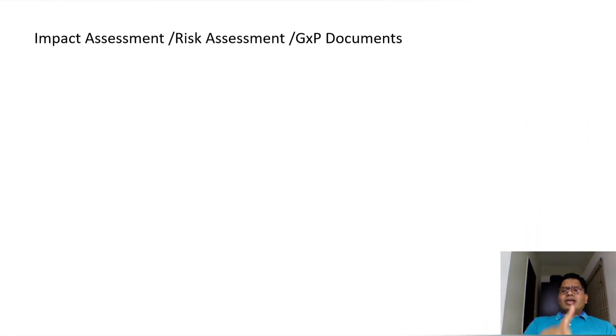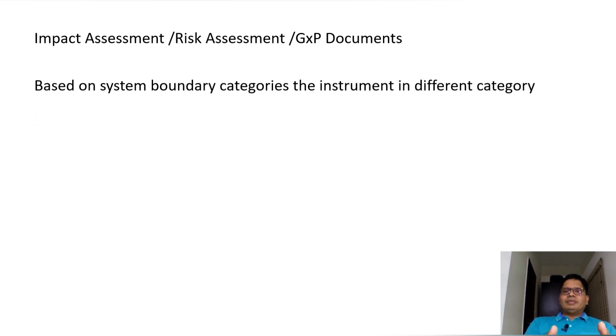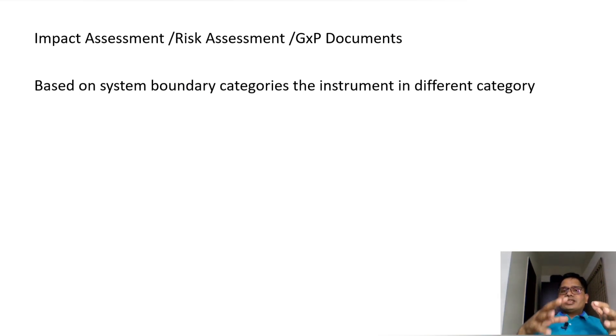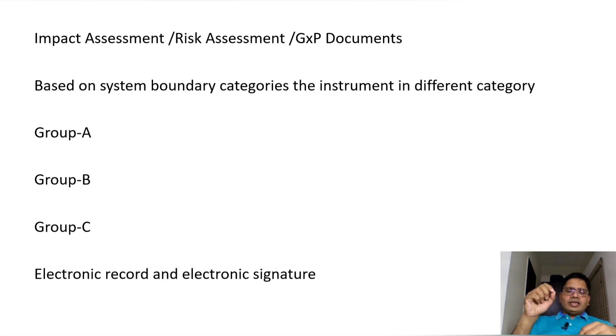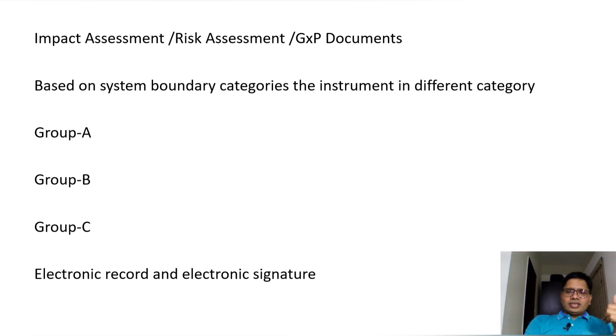To start instrument qualification, the first step is to perform an impact assessment, also called a risk assessment — a GMP document based on the system boundary. The system boundary covers the capabilities of the instrument: whether it is attached with software, whether it has measurement capability, and so on. Based on the GMP document, you first identify whether the instrument is Group A, Group B, or Group C. Then you check if there is software or internal memory, and whether the instrument has electronic record and electronic signature capability.